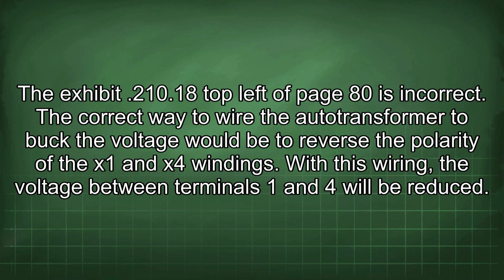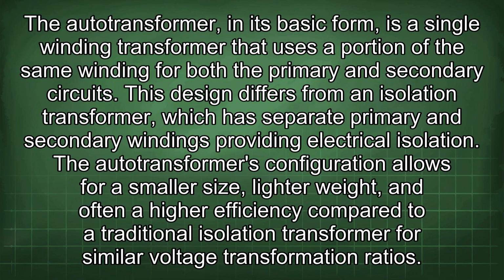The correct way to wire the autotransformer to buck the voltage would be to reverse the polarity of the X1 and X4 windings. With this wiring, the voltage between terminals 1 and 4 will be reduced. The autotransformer, in its basic form, is a single winding transformer that uses a portion of the same winding for both the primary and secondary circuits. This design differs from an isolation transformer, which has separate primary and secondary windings providing electrical isolation.